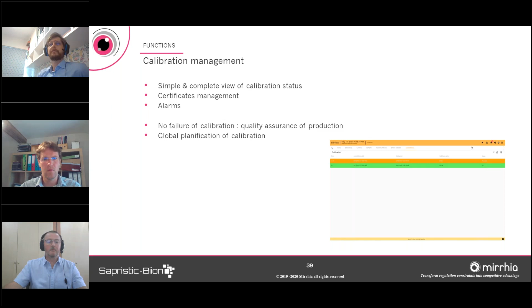This is the configuration tools that you get with Mirrhia, which allow the scalability of the software and configuration, and all those configurations have an audit trail, so we know what was changed and when. So we need user requirements to configure properly, but once it's configured, adding a probe, a particle counter, or an equipment is all done at this configuration level using validated functionality. Our validation of the software solution is just to make sure the right configuration has been implemented and that the signal is coming fully into the software.